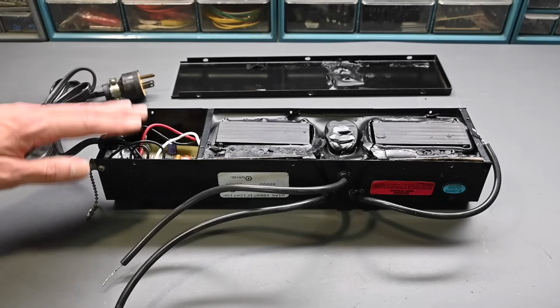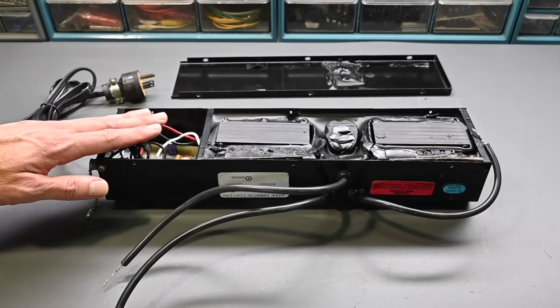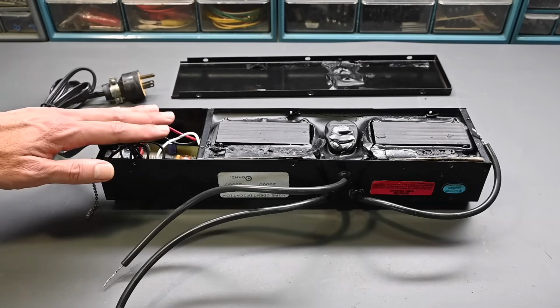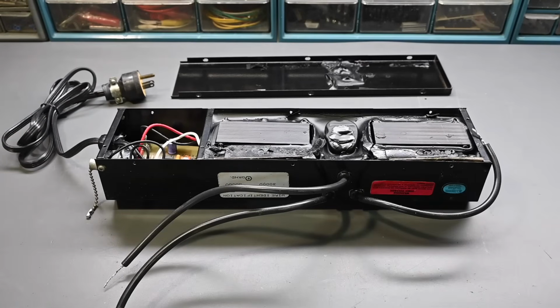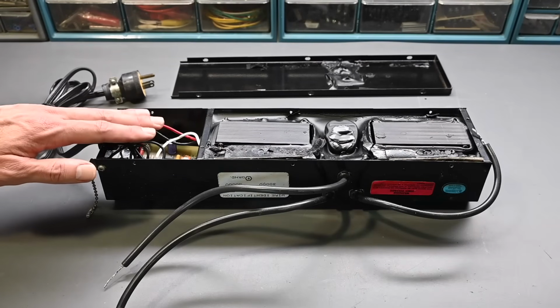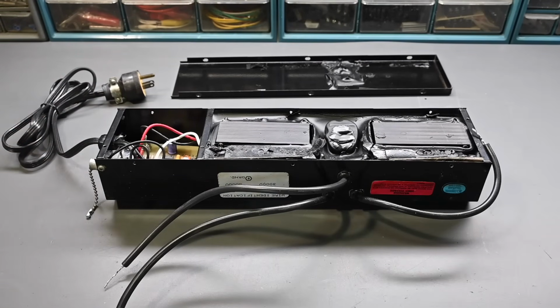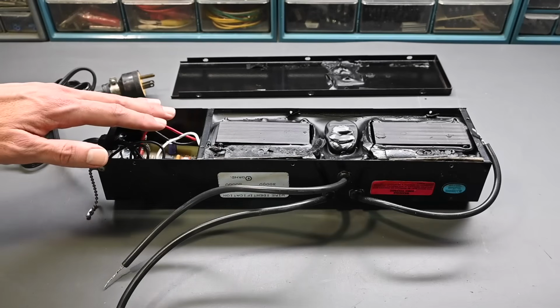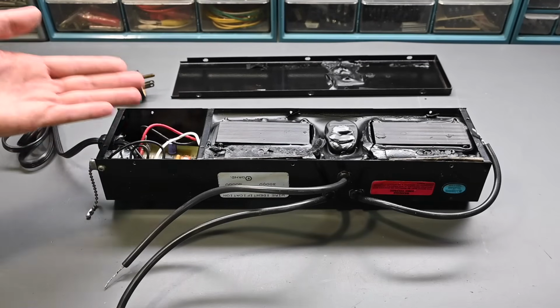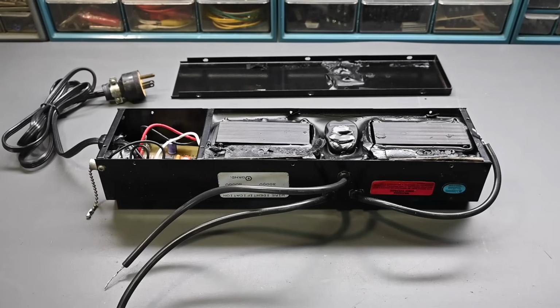Now on this control board, there's another problem you have to be careful of when troubleshooting: nothing is electrically isolated on that board. There's some circuitry in here that operates at a much lower voltage than the AC line, and there are components that step that voltage down, or drop the voltage would probably be a better way to say it, because it's not being stepped down like through a transformer.